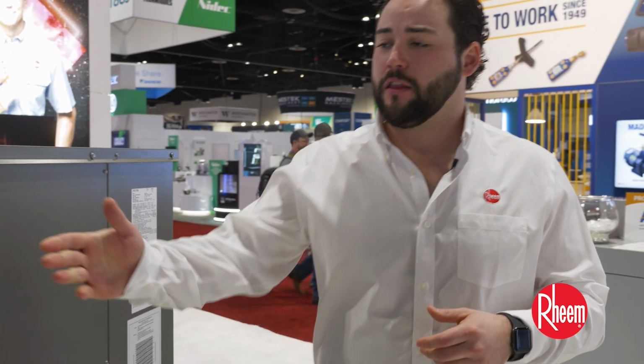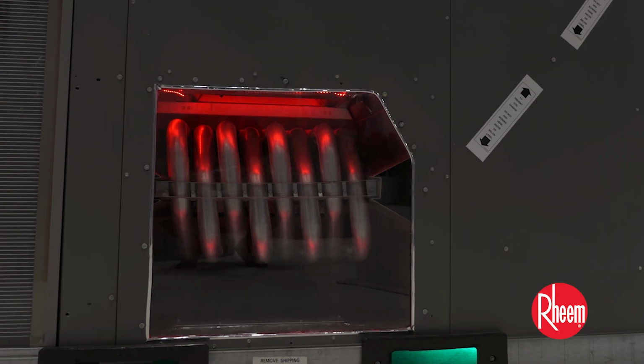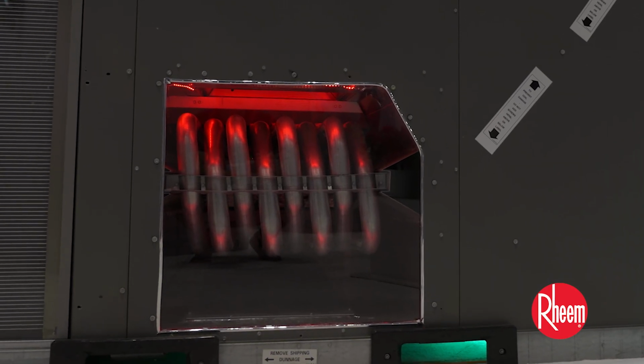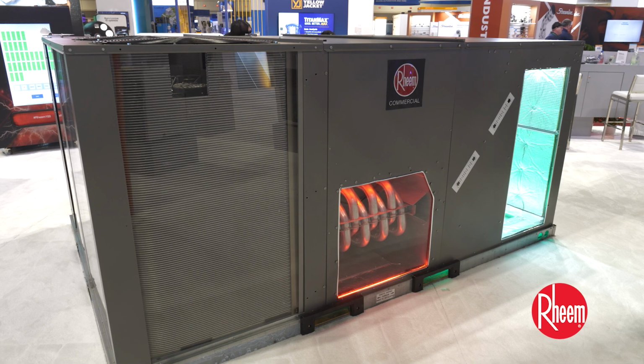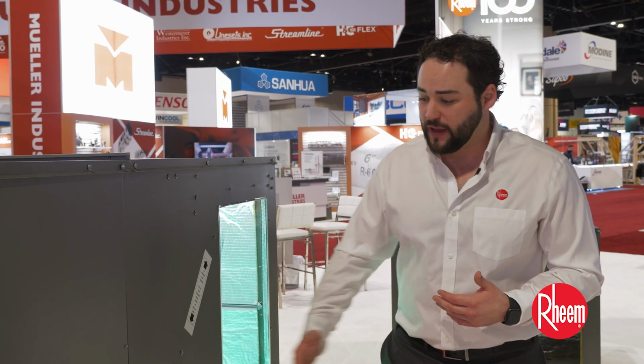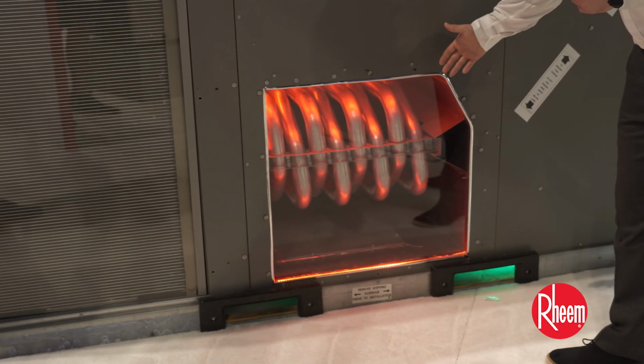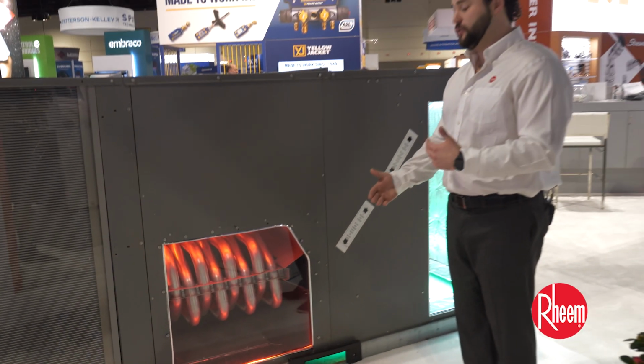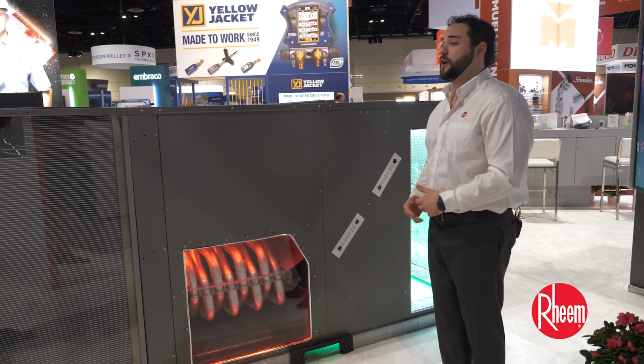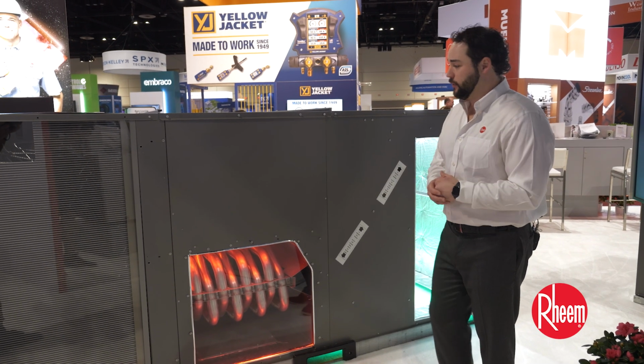Moving to the far side of the unit here, we have what we call our VelociFin heat exchanger. This is a patented technology that allows us to have a better input and output ratio on our gas heat exchanger. What you will notice, however, compared to a lot of the other manufacturers in the field, is that our heat exchanger actually sits on a slide-out chassis. What this allows you to do is actually, like the fan, slide the heat exchanger out, inspect it, or replace it if necessary with minimal effort in the field.